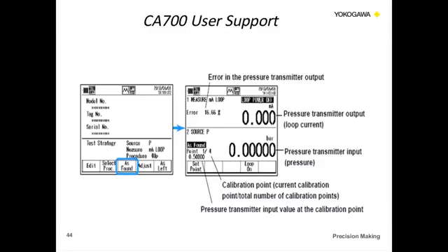So as you go through it, on the right, that screen there is what you'll end up doing: the source pressure will change, and you'll go through different points. And once you hit that set point, you'll go ahead and hit that set point button, and then go up to the next point, and so forth.